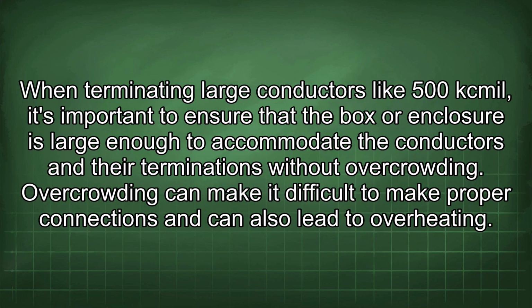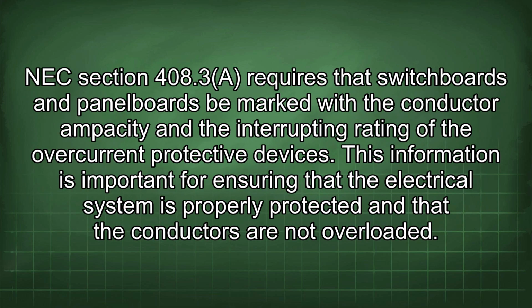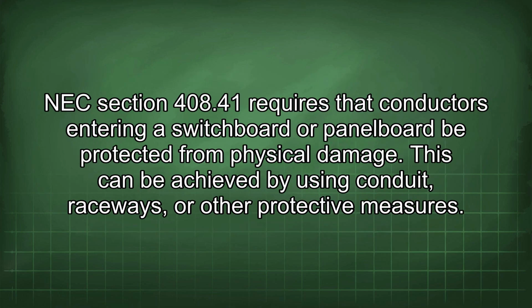When terminating large conductors like 500 kcmil, it's important to ensure that the box or enclosure is large enough to accommodate the conductors and their terminations without overcrowding. Overcrowding can make it difficult to make proper connections and can also lead to overheating. NEC Section 408.3 requires that switchboards and panelboards be marked with the conductor ampacity and the interrupting rating of the overcurrent protective devices. This information is important for ensuring that the electrical system is properly protected and that the conductors are not overloaded. NEC Section 408.41 requires that conductors entering a switchboard or panelboard be protected from physical damage. This can be achieved by using conduit, raceways, or other protective measures.